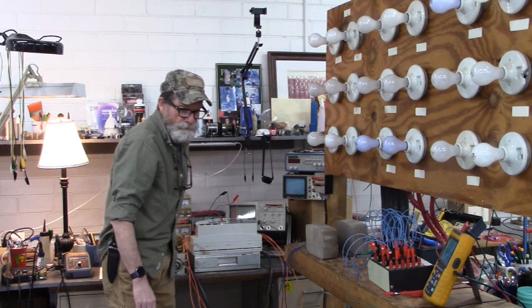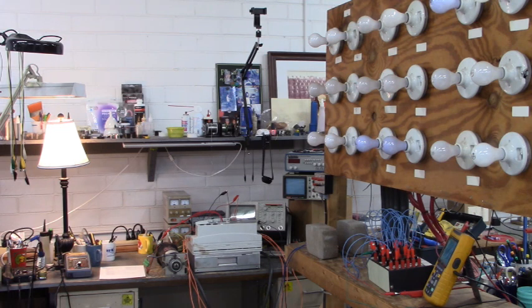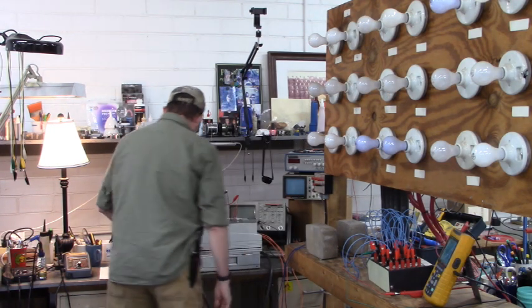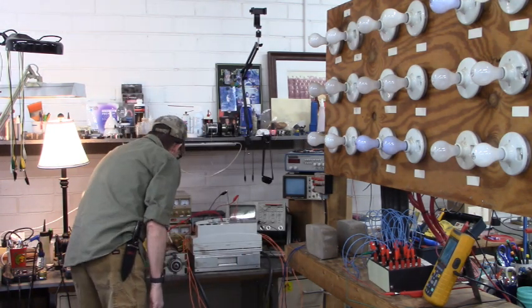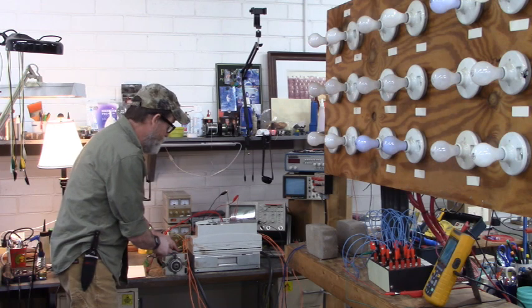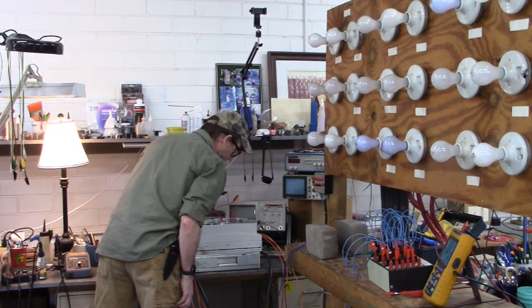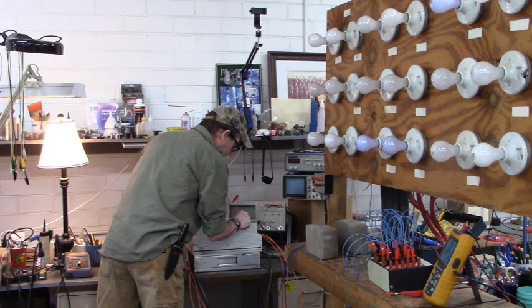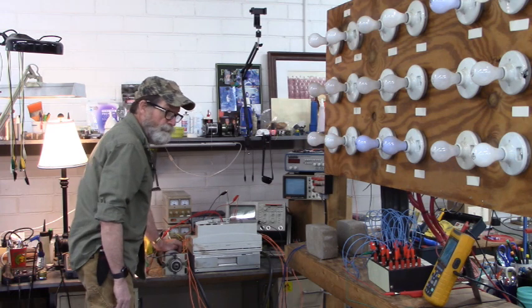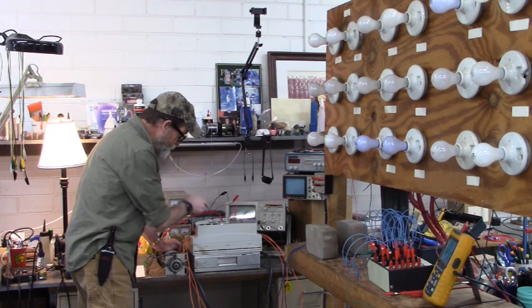Let me go around and we'll power up this drive with 380 volts AC three phase to L1, L2, and L3. Now, I'm going to turn on the DC motor. And it's rotating. We'll get closer to this so you can see it. And I can see 87, 86 RPM in the HMI panel. Human interface panel. So that feedback appears to be working.